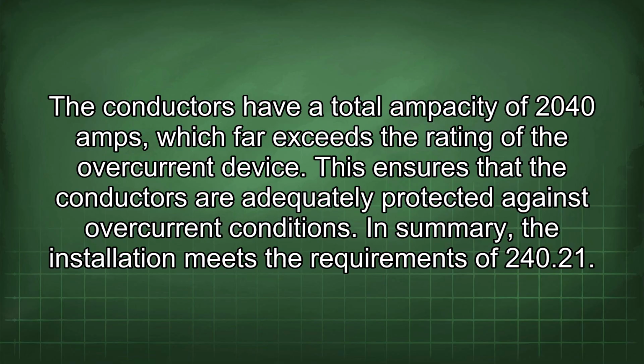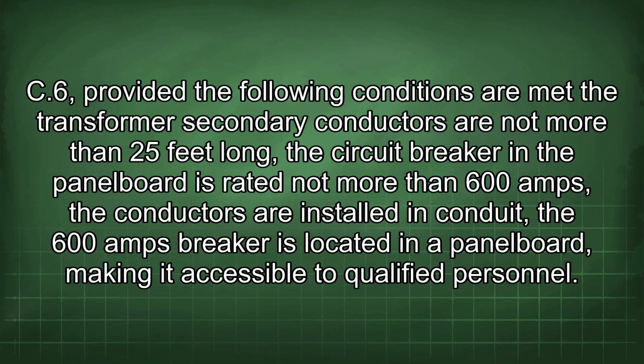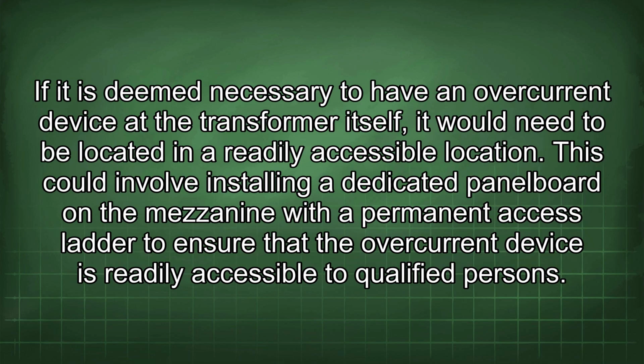In summary, the installation meets the requirements of 240.21(C)(6), provided the following conditions are met: the transformer secondary conductors are not more than 25 feet long, the circuit breaker in the panel board is rated not more than 600 amps, the conductors are installed in conduit, and the 600 amp breaker is located in a panel board, making it accessible to qualified personnel. If it is deemed necessary to have an overcurrent device at the transformer itself, it would need to be located at a readily accessible location.